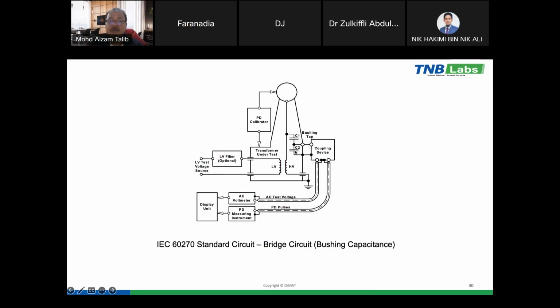Okay, here is the transformer. This is the bushing. Here there is a test tap, and then we tap through the bushing. We have a capacitor which will act as a coupling capacitor. So we connect our coupling device to the test tap, and then we inject the voltage. As I said, we inject the voltage at the LV, and then we measure at the HV. This is the process of how we inject the PD pulse during the calibration process.